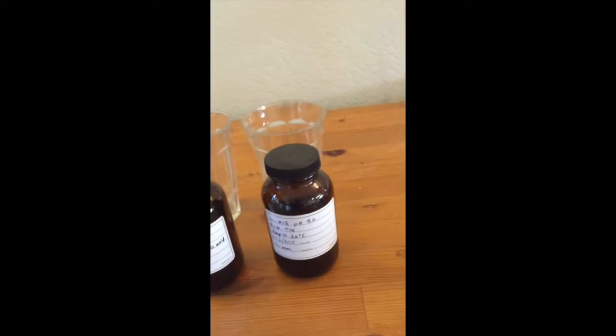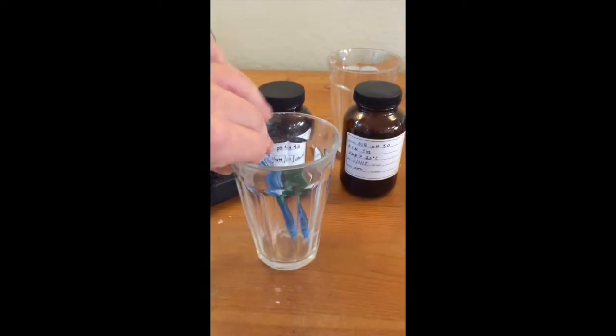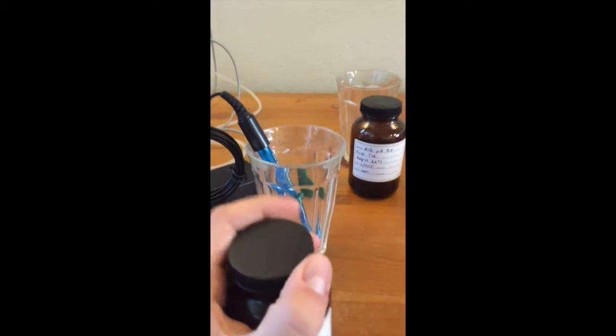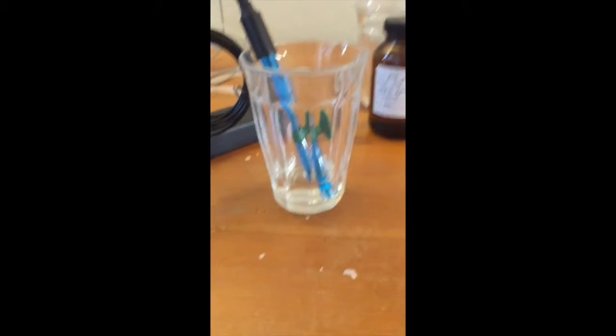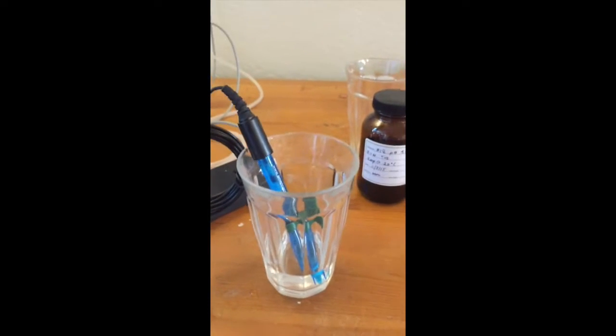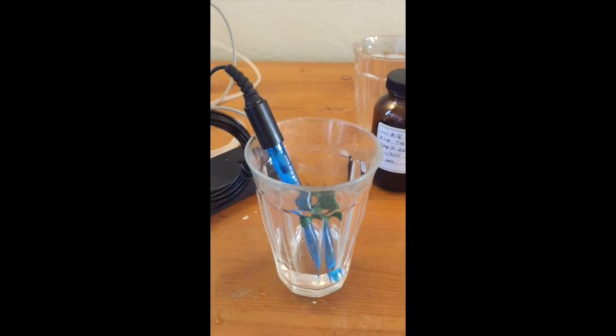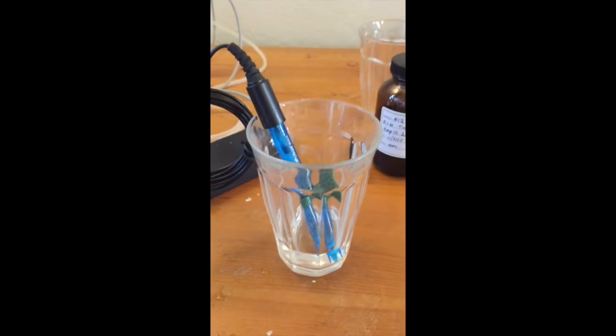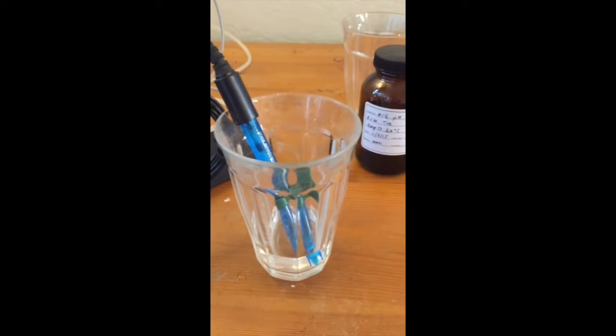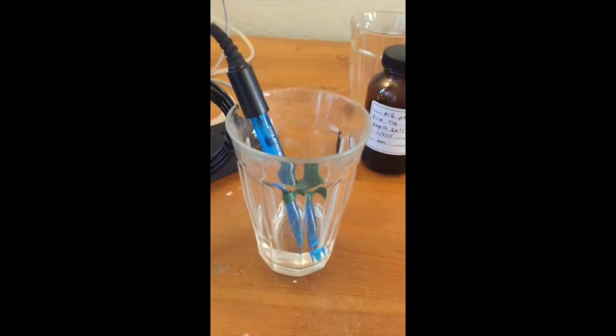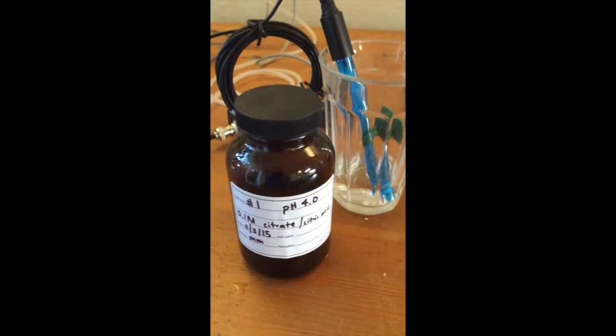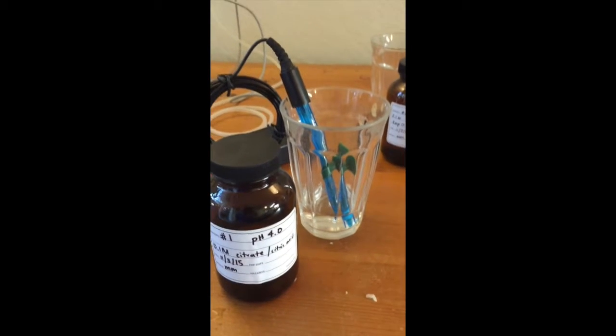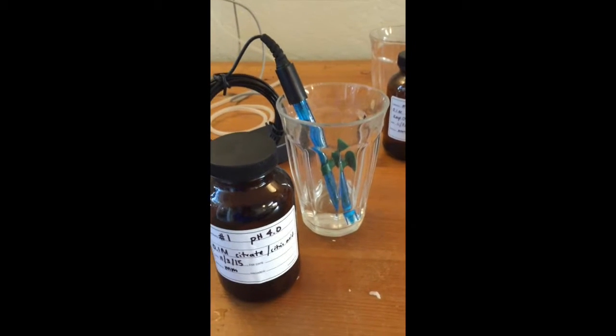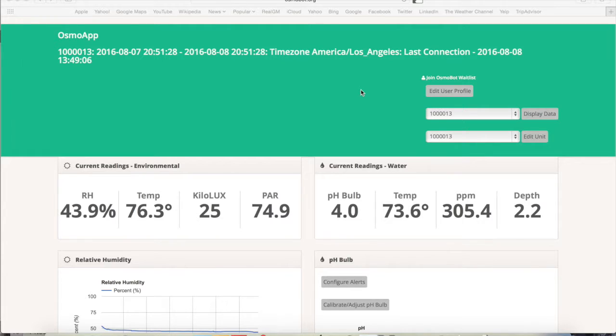What you do is you take your probe out of your system. You take some of your buffer solution, you make sure that the probe is sitting fully in the solution, and then you wait. How this works is the probe sits in the solution, and you actually use the raw data from the OsmoBot to recalibrate it. So every 15 minutes your unit's going to take up a reading, and then we can go online to see what that last raw data reading point was for this 4.0 solution, and then take that reading and enter it into the database so it can correct the algorithm should the probe need recalibration. Now let's get back to your dashboard.